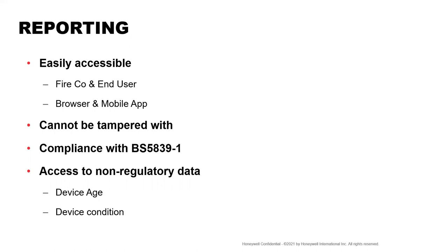Device condition. Certain devices in certain areas, like in warehouses and whatever, their condition is going to deplete much quicker than that of one in an office, probably because they're going to be subjected to dust and all that kind of stuff. So it's important that you can see the device condition, because although it says that you can have a detector there for 10 years, it might be that in the particular environment in which it's put, it might only last seven, and then it goes to its thresholds and been able to clean itself and whatever, and you might need to change them then.